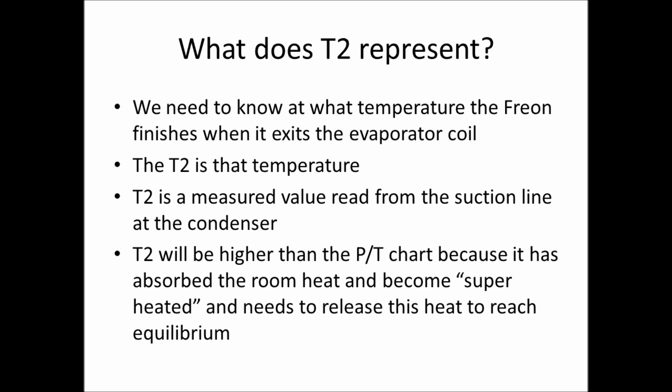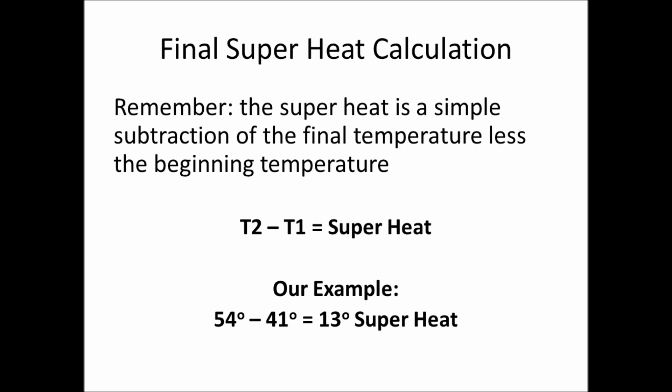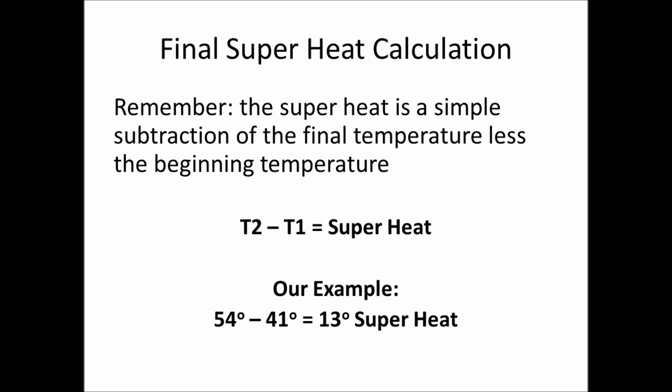T2 is a measured value from the suction line. It can be higher than what's shown on the pressure-temperature chart because the freon has absorbed the room heat, becomes superheated, and needs to release this heat. So the final superheat calculation is simple subtraction: in our example, 54 degrees minus 41 degrees equals 13 degrees of superheat.